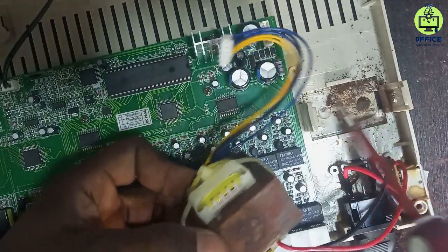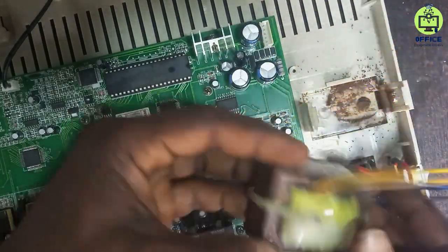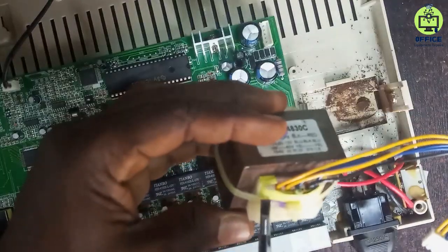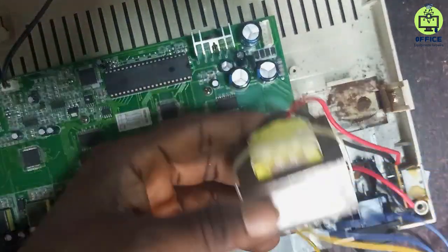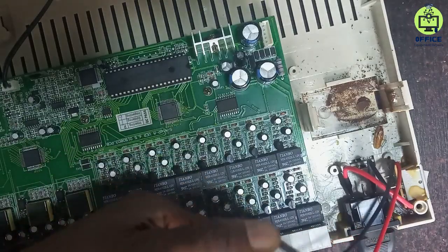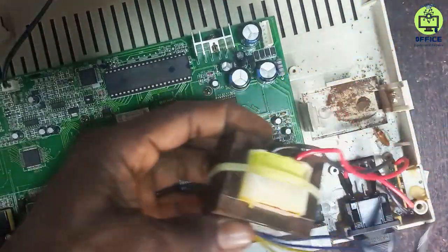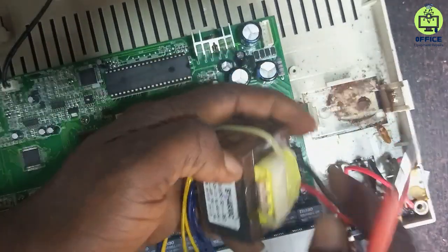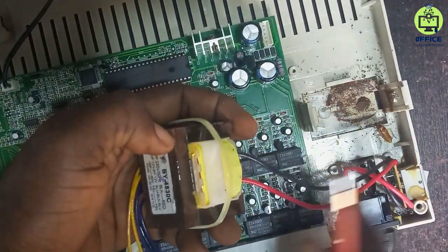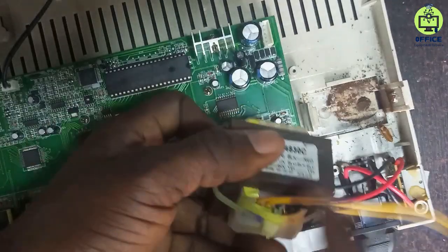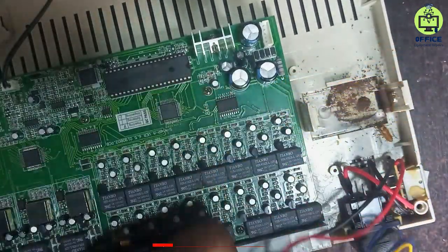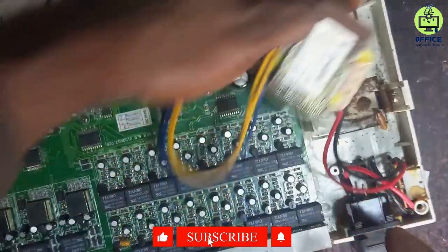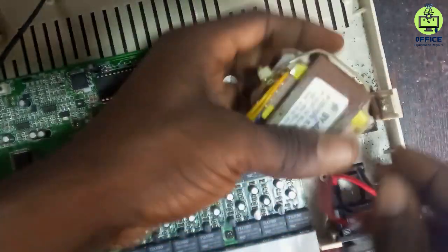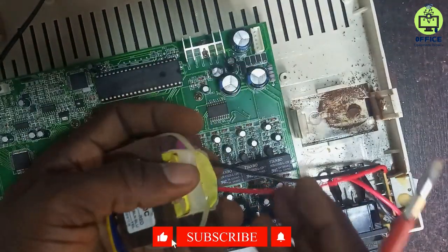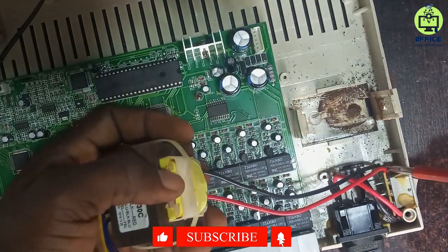Otherwise, if you don't know how to do that, you can see this rust here. That means this transformer has been sitting here for a very long time, probably water damage, or a cockroach or insect died around there, and that produced some kind of liquid that breached the primary end of this transformer. So something is definitely wrong somewhere. You can see we have some cockroaches around there, so likely an insect died, and that is the reason for those rust signs.